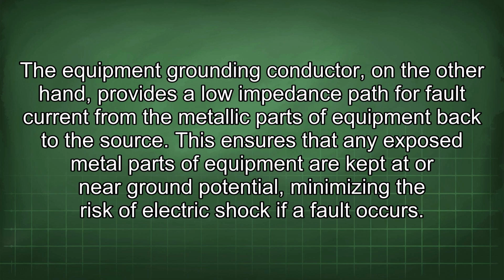The equipment grounding conductor, on the other hand, provides a low impedance path for fault current from the metallic parts of equipment back to the source. This ensures that any exposed metal parts of equipment are kept at or near ground potential, minimizing the risk of electric shock if a fault occurs.